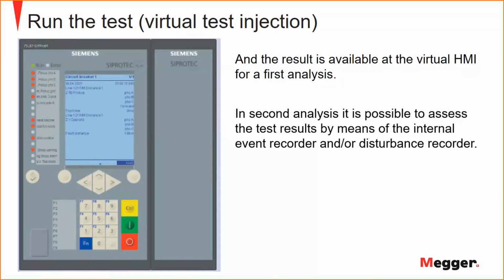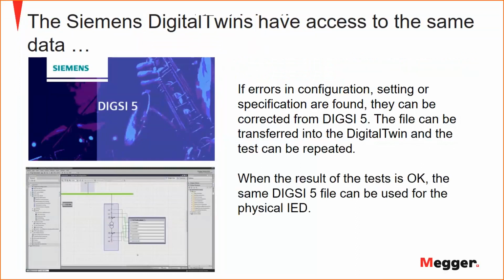As you normally do, many tests use the disturbance recorder also in substations. So if you find errors in configuration, which you will find, they can be corrected from the DIGSI file. You can transfer the data into the digital twin, and then you can repeat the test until you are happy. And when the result of the test is okay, the same DIGSI 5 file can be used for the physical device, for the physical protection relay. What did I say?